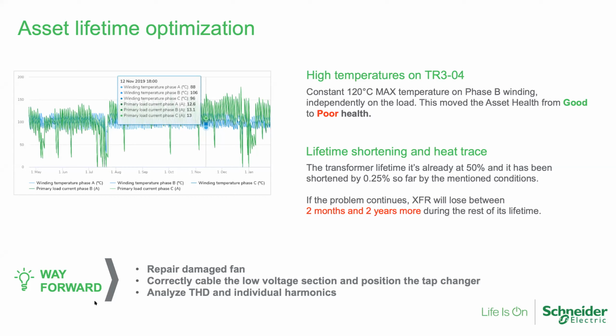What your historian, SCADA, or HMI cannot do is combine different pieces of information like historical loading, the temperature it's running at, environmental conditions, etc., and use these to detect how much of the transformer's life we're adversely affecting by running it under non-nominal operational conditions. So we're taking life away from this transformer. Why is this important? To know if we're aging a piece of equipment faster than we should, because that affects total cost of ownership.